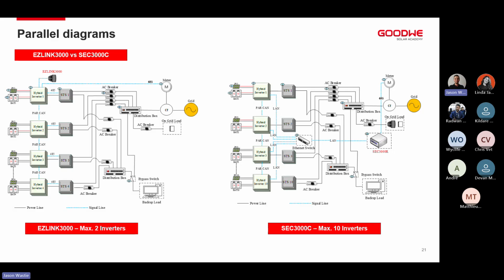There's a few other benefits of using the SEC3000C controller. One of them, for the city of Cape Town specifically, we had a case not too long ago where they need to have full control of your system remotely to be able to shut down the system or control the power flow through the inverters itself, because they are allowed to export back to the city. In the past, you would need to use a third-party logger or third-party controller that has got IEC 104 protocol compatibility. The SEC3000C controller has got IEC 104 protocol compatibility built into it, meaning that we don't need to use any additional controller.